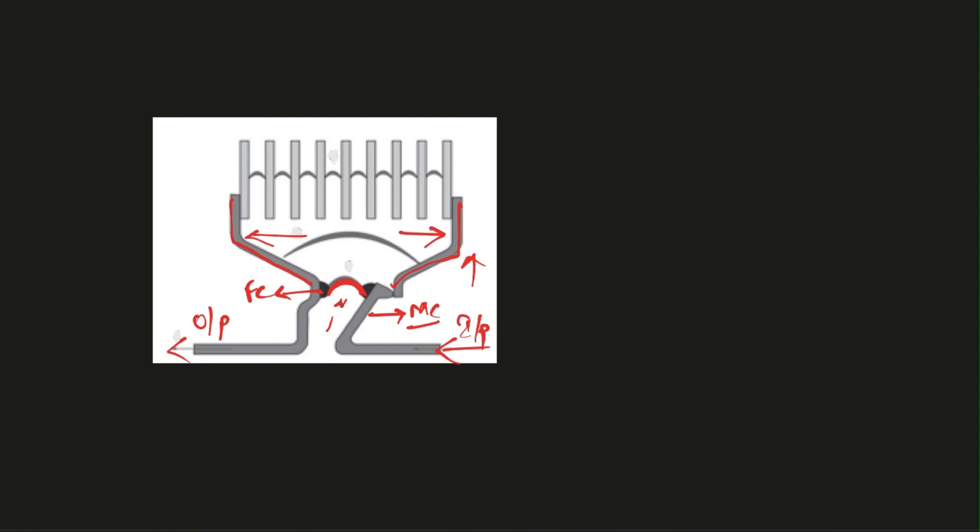As the arc is going upwards, the arc extends itself in length, and these arc chutes are made up of ferromagnetic materials. So this arc chute attracts this arc towards them. When the arc reaches this point, it starts to split into different sections because there are gaps between them.